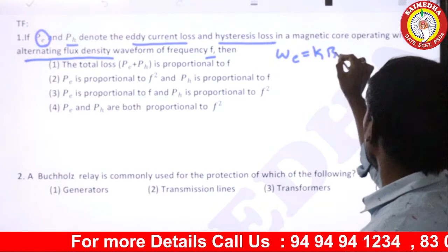If V by F is constant, then B maximum is constant and K is already constant, thickness also constant, so eddy current loss is directly proportional to frequency square.